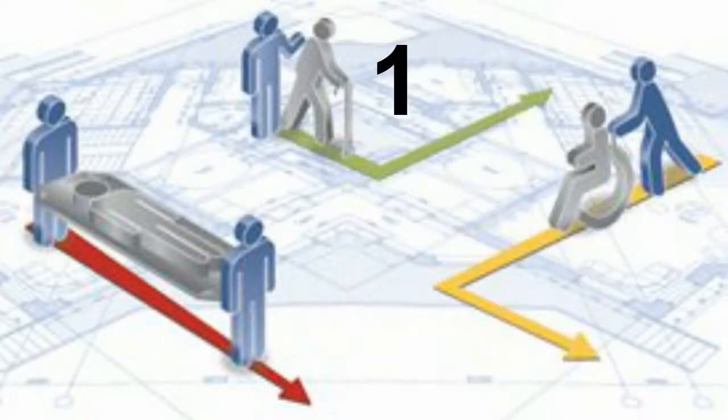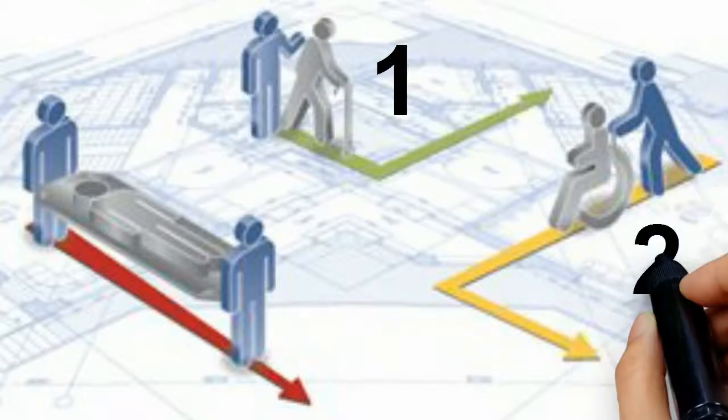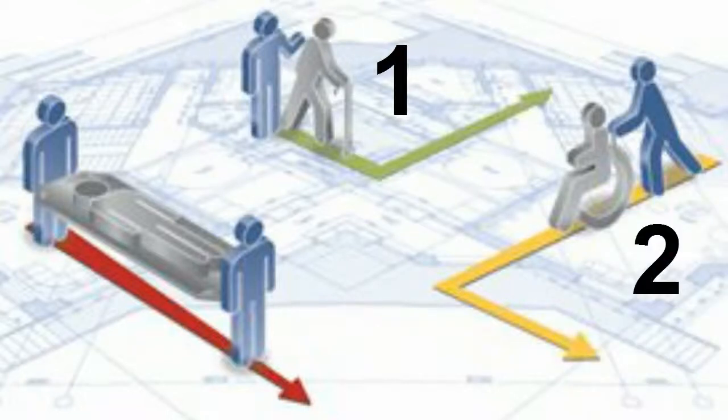Patients must be evacuated in the following order. First, ambulatory, those able to help themselves. Second, wheelchair assist. Third, bedridden patients. Assign an employee to lead a chain of ambulatory patients and visitors to safety. Evacuation should only take place if an order is given by the hospital administrator or someone who has the authority to do so.